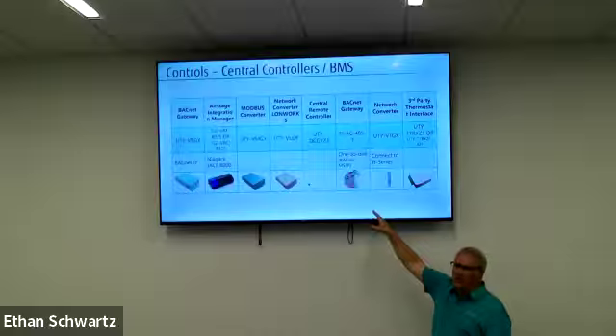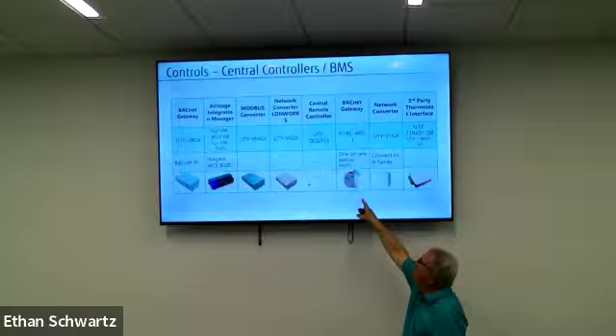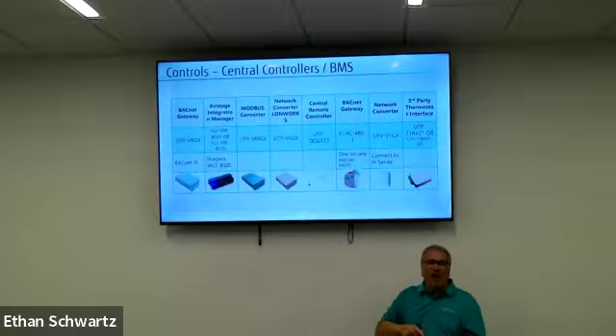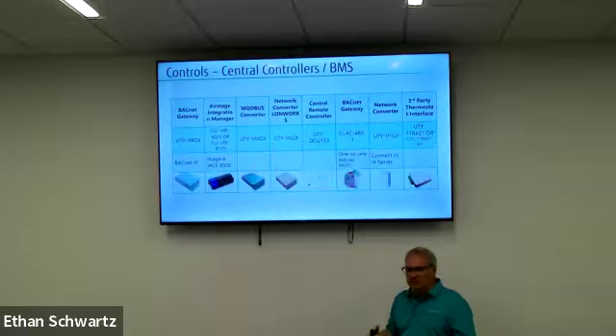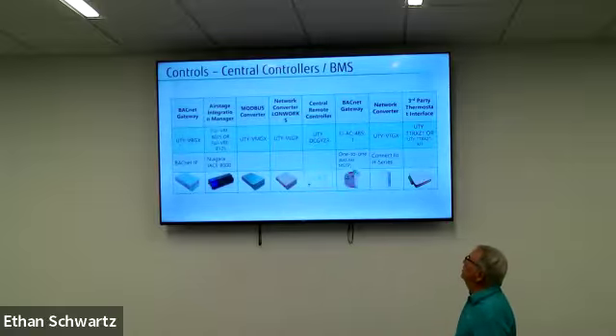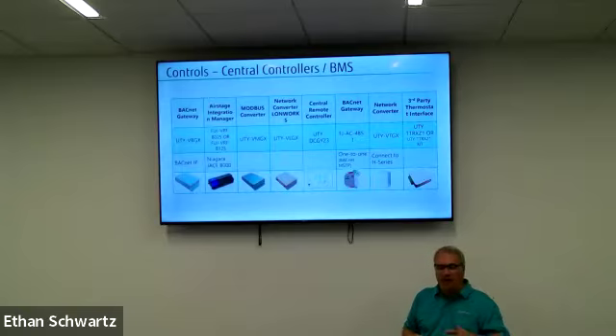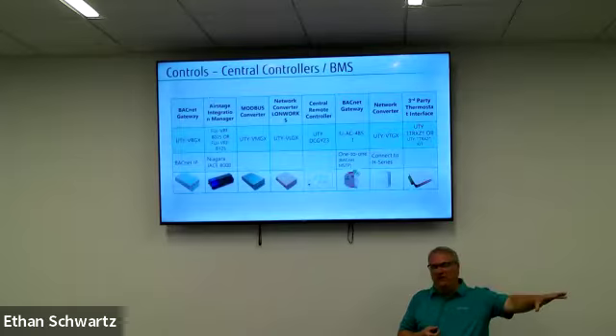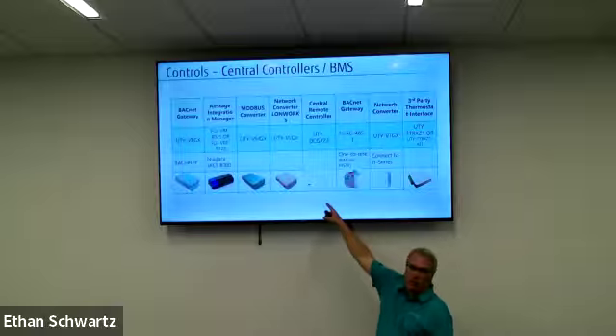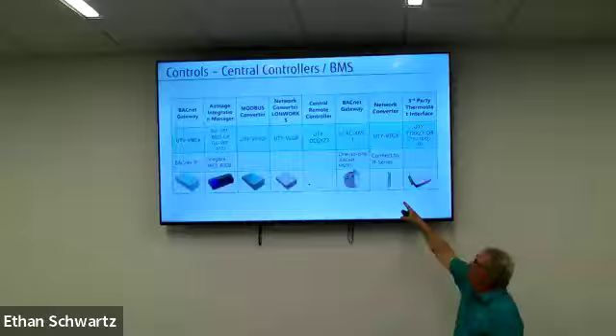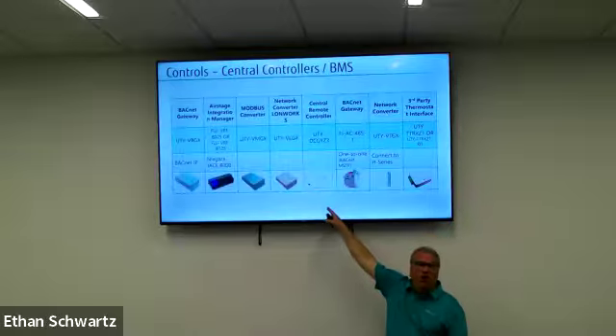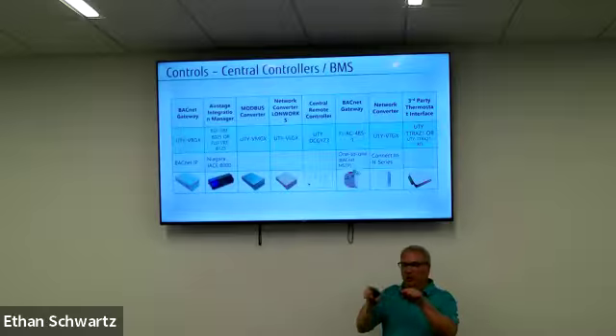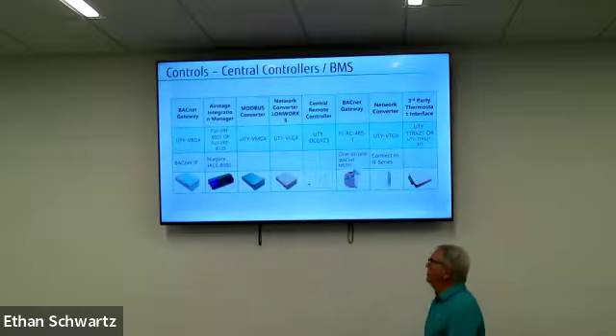But let's say you're doing the J7S on a 3-zone system, and you're in a school and they said, hey, we want to tie this into our BACnet system. You can put one of these on each indoor unit, and that will allow a BACnet DDC system to see that indoor unit and allow it to be controlled. If you have that lone unit in the computer room, that lone 18,000 BTU or 24,000 BTU unit, and you have a VRF system and you have a central controller, this adapter converter allows it to be a visible zone on the VRF control network so that they could still change fan speed, mode, whatever they wanted to change.